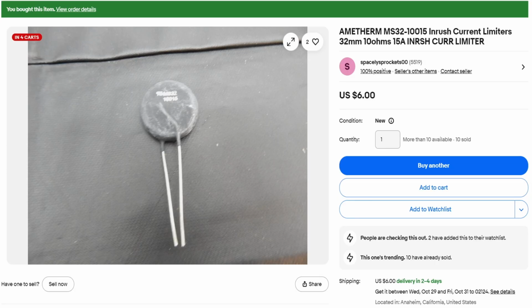So I purchased an inrush current limiter rated for 15 amps at 10 ohms. 10 ohms is nominal at 25 degrees Celsius - they're basically negative temperature coefficient resistors. As they get warm, the resistance drops. So they help block the inrush current when cold, then they heat up from the current flowing through them and conduct electricity a lot better, so that when you're pulling 15 amps through it, its resistance is only 0.1 ohms.